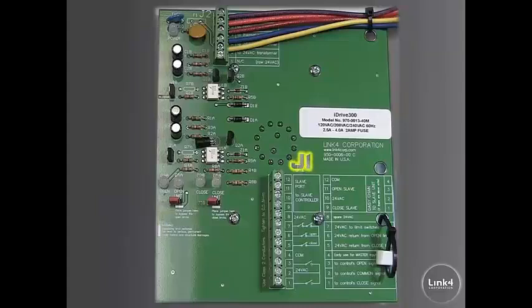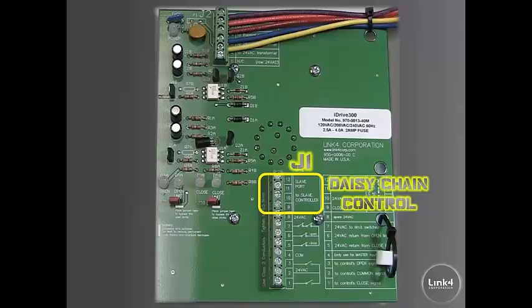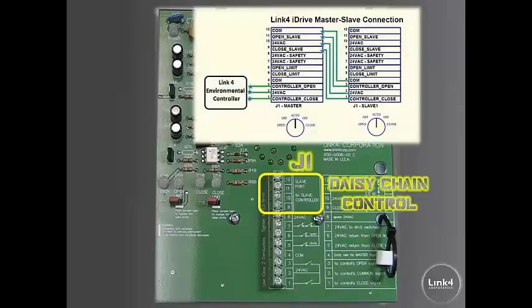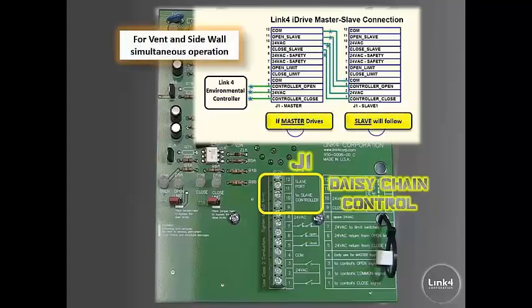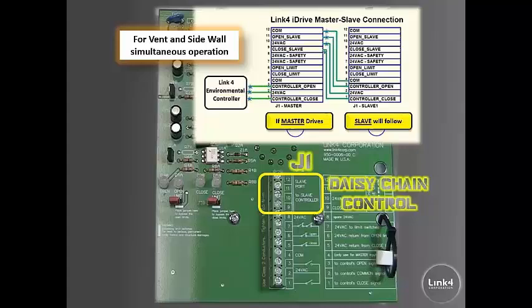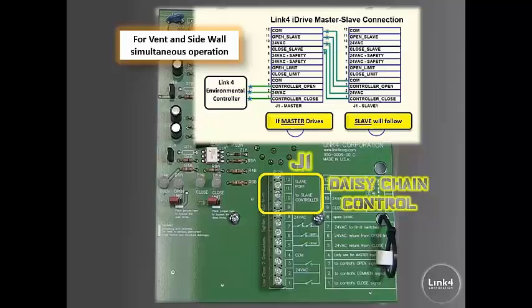On the J1 portion of the circuit board, you have daisy chain control, which allows you to daisy chain multiple controllers together. You can have up to four iDrives in one continuous chain. If the master drives, the slaves will follow. This is commonly used for vent and sidewall simultaneous operations. You take the J1 section 9 through 12 of the master and daisy chain them to the J1 section 1 through 4 of the following iDrive and so forth.